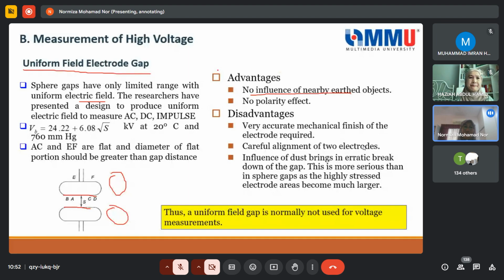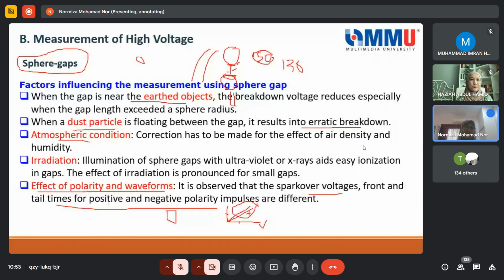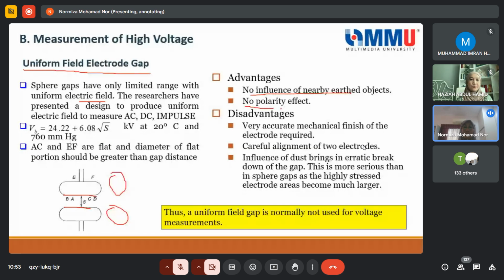And then another disadvantage of the sphere gap is the polarity. So the advantage of this is no polarity effect. But of course, this equipment is mainly for research, so a very accurate mechanical finish of the electrodes is required, because you can see that it has a larger surface here. You have to make sure that these are uniform and that this is aligned. If this is at this point here, then it should be at this point here as well. So it has to be arranged correctly in the construction of this uniform field electrode gap. So careful alignment is needed, and then the influence of dust.